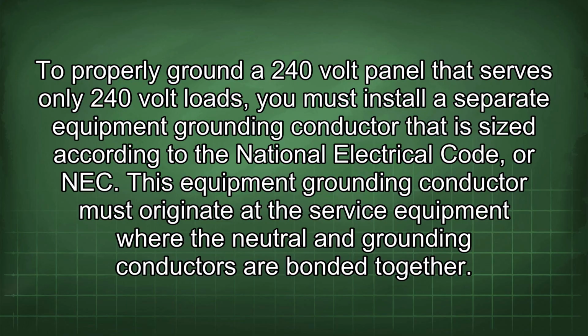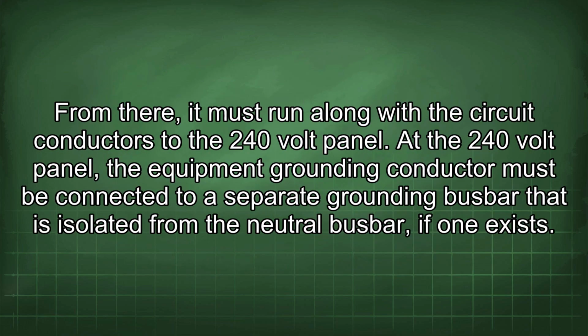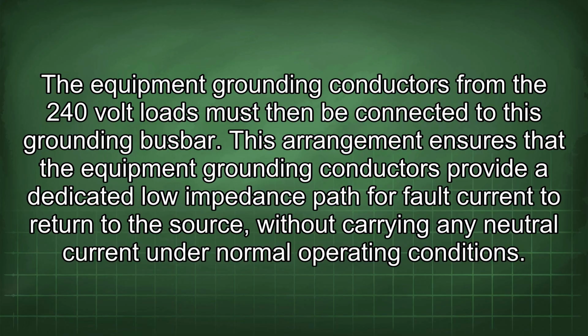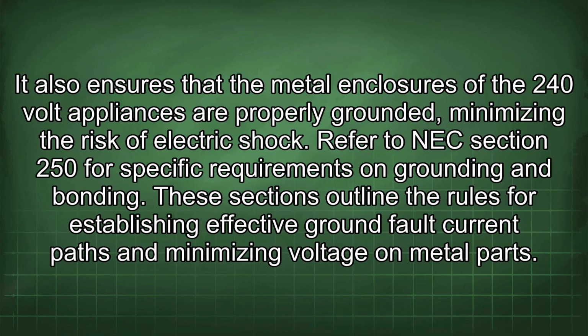This equipment grounding conductor must originate at the service equipment where the neutral and grounding conductors are bonded together. From there, it must run along with the circuit conductors to the 240-volt panel. At the 240-volt panel, the equipment grounding conductor must be connected to a separate grounding busbar that is isolated from the neutral busbar, if one exists. The equipment grounding conductors from the 240-volt loads must then be connected to this grounding busbar. This arrangement ensures that the equipment grounding conductors provide a dedicated low impedance path for fault current to return to the source, without carrying any neutral current under normal operating conditions. It also ensures that the metal enclosures of the 240-volt appliances are properly grounded, minimizing the risk of electric shock.